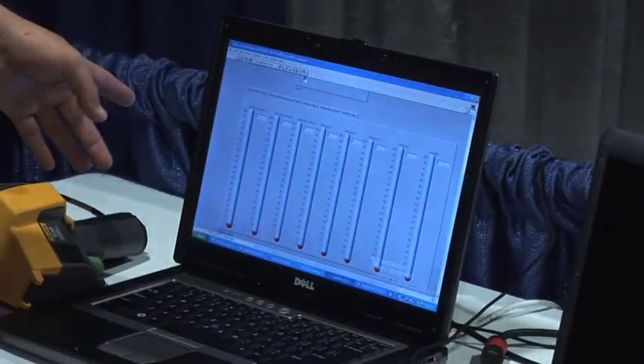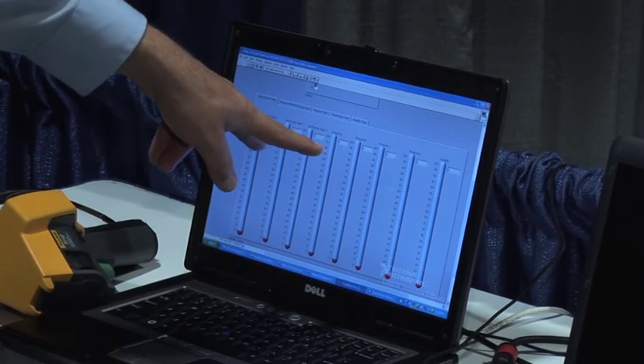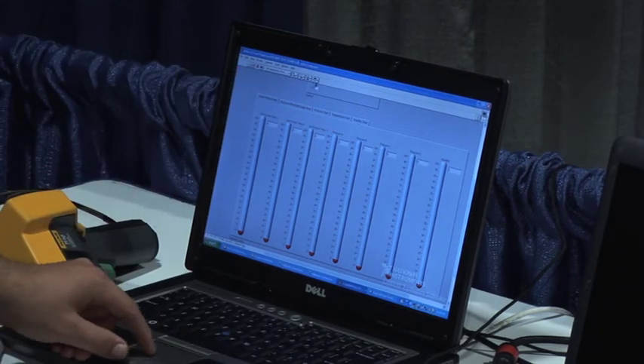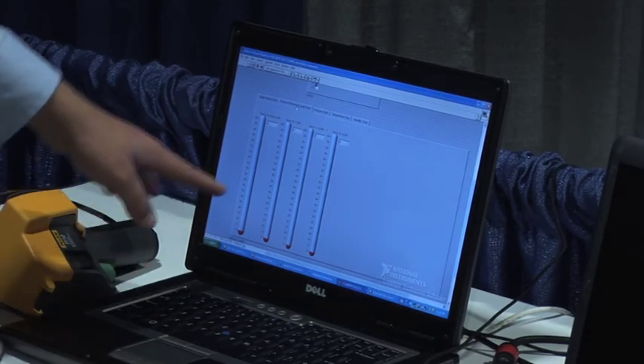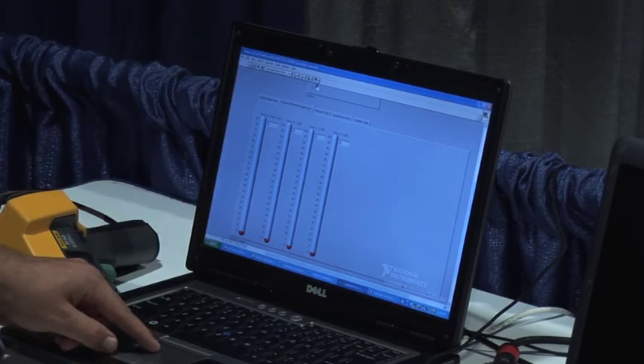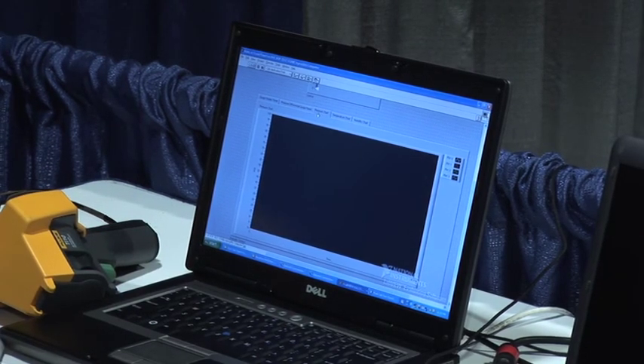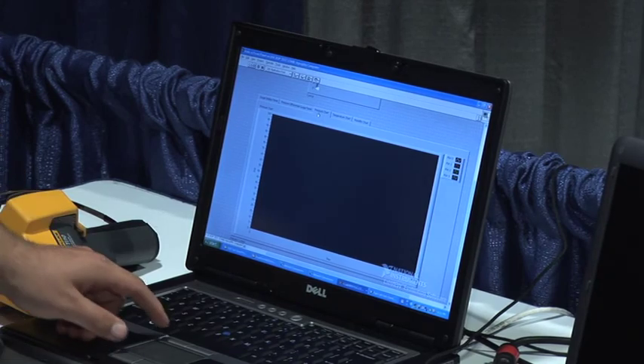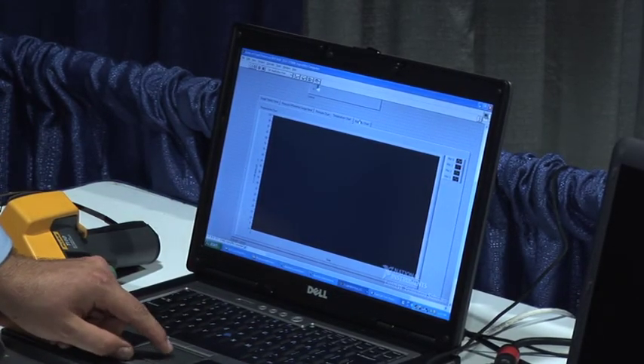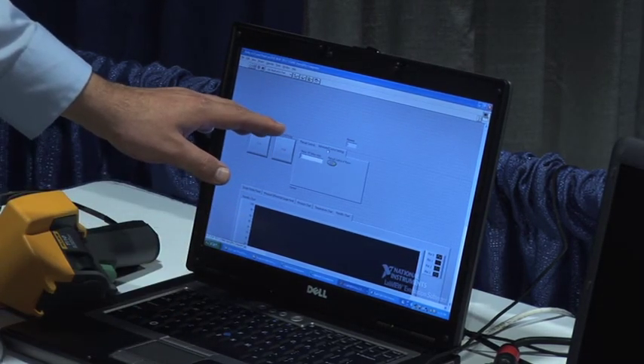As you can see, we have our gauge panel here. So we go through and we have our three gas process temperatures, our four major pressures in our system, and then our humidity. After that, we also have our pressure differential gauge panel, which is going to give us our difference in pressure from inlet to outlet of different components. From there, we have our two charts that we're graphing our data, and then this is all compiled out to a TDMS file for using the data later on. And our temperature chart and humidity. We're starting to get into automation right now. I just had something basic set up, just take off manual control, and it'll run on its own for a little bit.